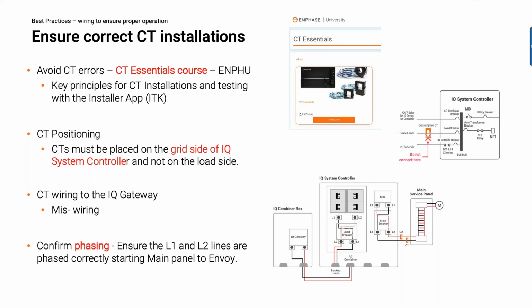I think most of you know that CTs are a critical part of installing any Enphase backup type system. So if you're doing any system that's putting IQ batteries in or IQ8 PV for backing up a system if the grid goes out, you have to have that system fully configured with CTs, and they have to be 100% correct. And the reason we're mentioning that is that there is a high degree of errors incurred when installing systems, and a lot of those are around installing the current transformers, all right, and metering. So why do these errors occur?